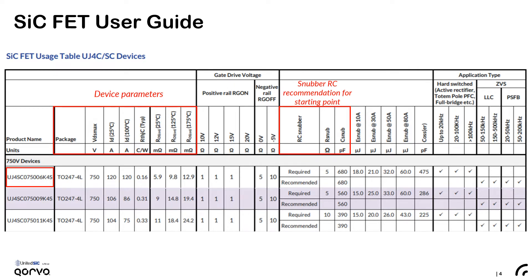For example, for the 6 mΩ 750V Gen4 device, which is the first row, we require a snubber for hard switching and a starting RC value is provided. But for the same device in soft switching, we only recommend snubber capacitance, so there is no snubber resistor in series. And this device is good for all hard and soft switching applications listed here.